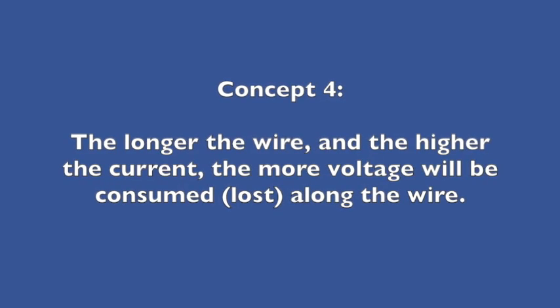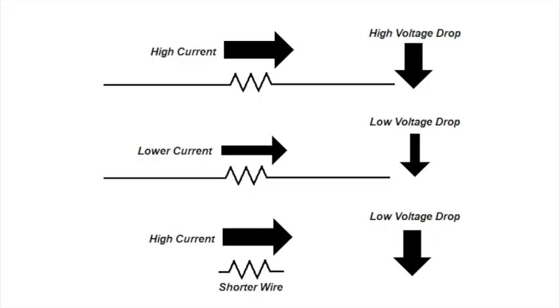Concept four, the longer the wire and the higher the current, the more voltage will be lost along the wire. To prevent this voltage drop, you must either reduce the length of the wire or increase the size of the wire.